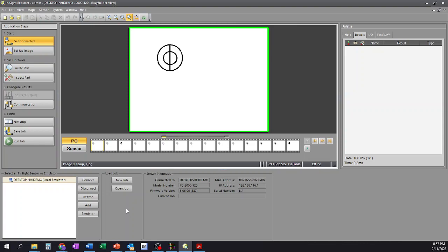Sometimes it's nice to hide that in a different subnet, so that say you have one machine that has several different drives all connected to the same thing, and you don't want that camera communicating as much, you put it in a different subnet so that it's not communicating as much across those networks. Cameras do have a tendency to cast a lot of communications throughout that network at short intervals of time, and they can add a lot of traffic to your other equipment on that network. Definitely something to keep in the back of your mind.